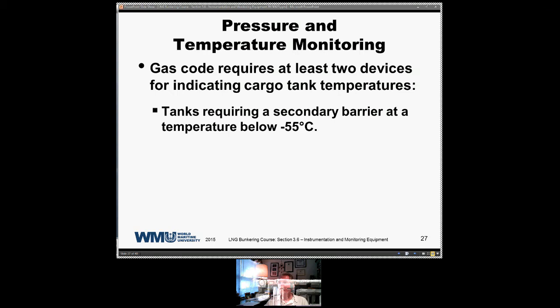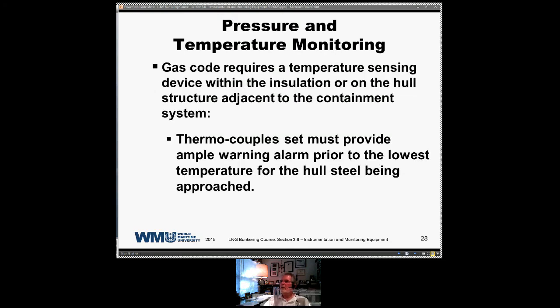The gas code requires at least two devices for tanks requiring a secondary barrier at a temperature below minus 55 degrees. So you're not only monitoring inside your tanks, you're monitoring external to the tanks in the barrier spaces, the secondary barrier. These temperatures are monitored at all times because temperature would be an indicator of a potential leak. So you have to monitor your temperatures in your barrier space as well as the insulation spaces.